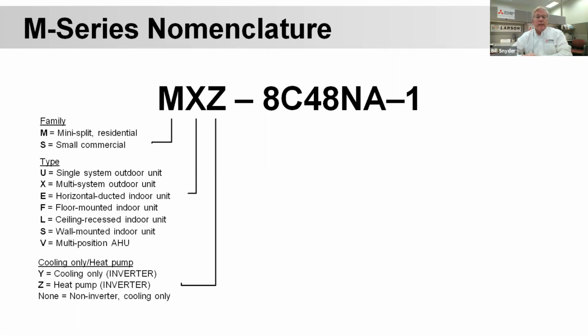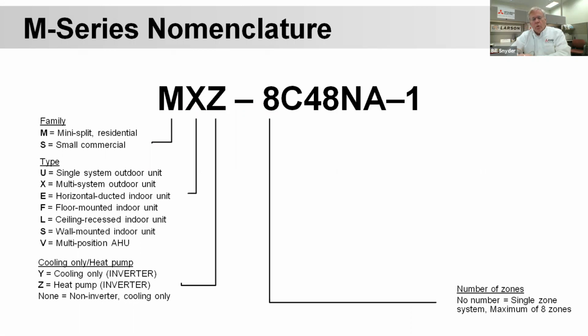And I like to think of Y as like the yellow wire on the thermostat. It's one of the ways I remember things. Typically on conventional systems yellow is a call for cooling. So MUY or MUZ would be an outdoor single, what we call 1-to-1, one outdoor unit, one indoor unit. If it was an MXZ, the X is a multi-system outdoor unit. In other words, you can have one outdoor unit that's capable of controlling multiple indoor units. In this case, the MXZ 8C, the 8 would indicate that it can control up to 8 indoor zones. You have to have at least 2 indoor zones minimum. Don't have to put all 8 on there, but you have to have at least 2 on any MXZ system.